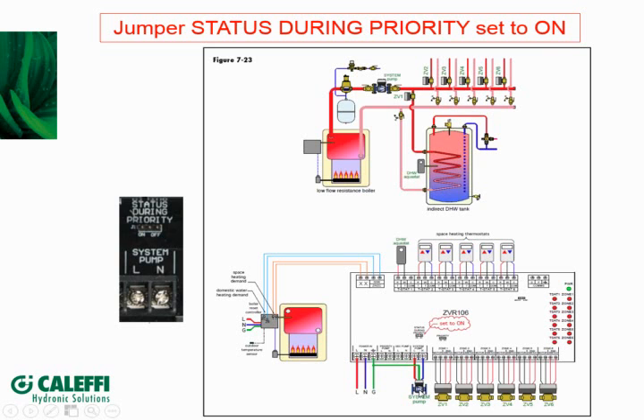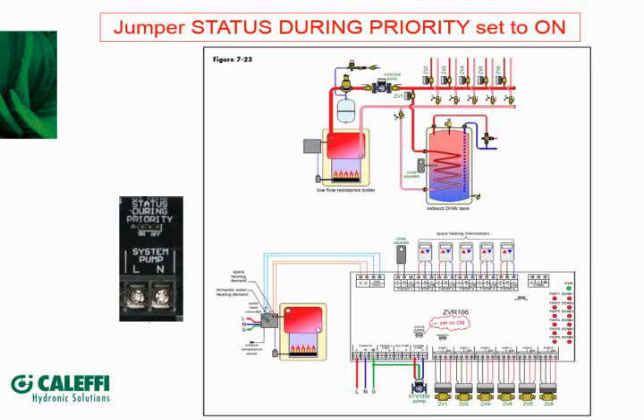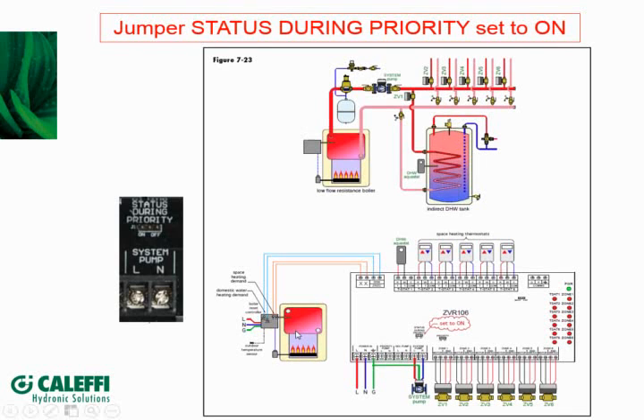Well, in this case, when the indirect calls, and I only have one pump in the system, and that's connected to my system pump. So when priority calls, I have to have that pump running. So in this case, the status during priority is set to on, so that it can move the fluid through the valve and through the boiler. And the boiler knows to go to high heat because the ZR ZC contacts have closed, taking the boiler off of its reset curve. Once it's satisfied, that opens up, and this zone valve number 1 closes, and then any of your space heating valves can then take over again. So hopefully that's clear what we're doing.